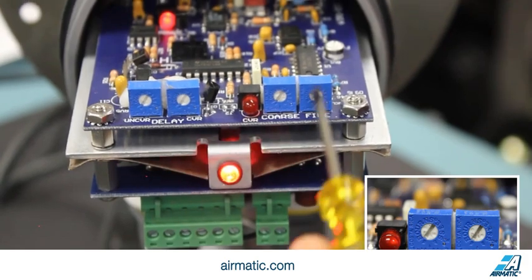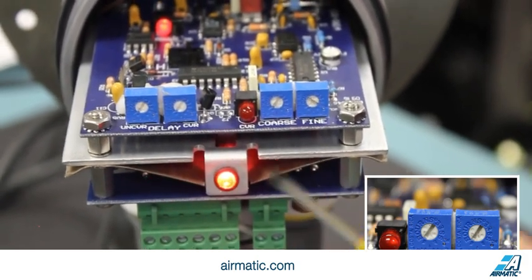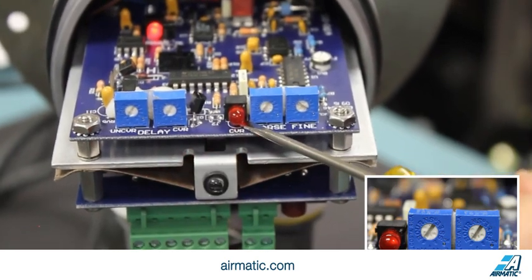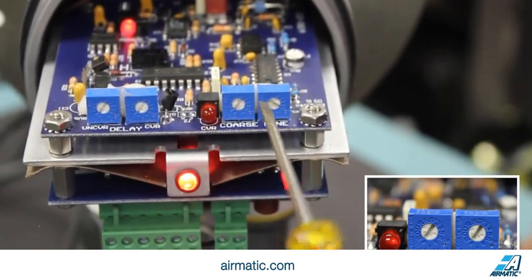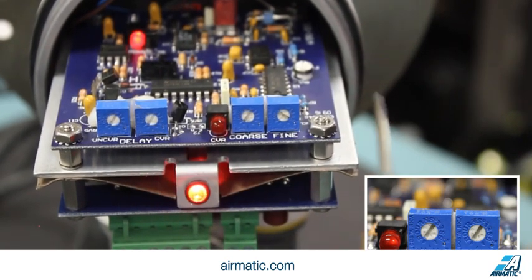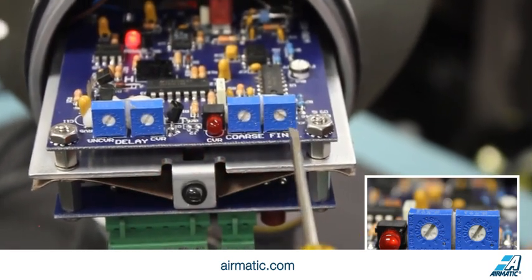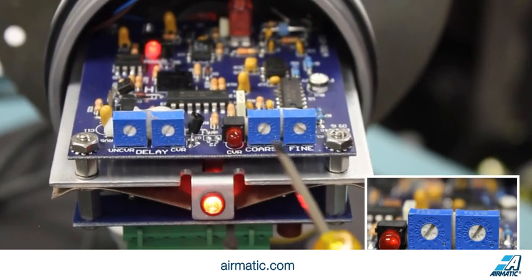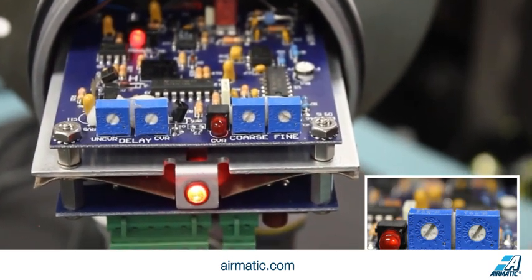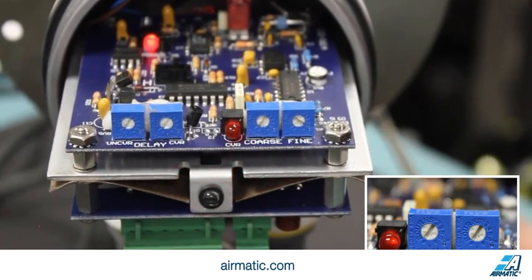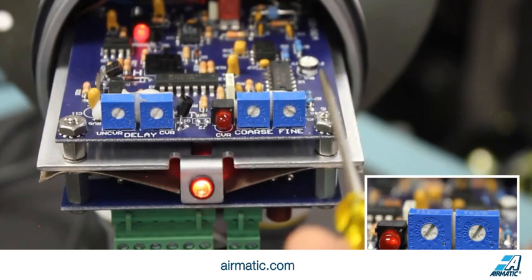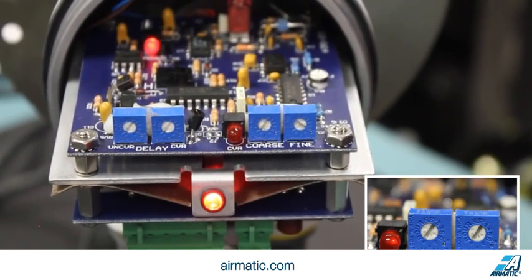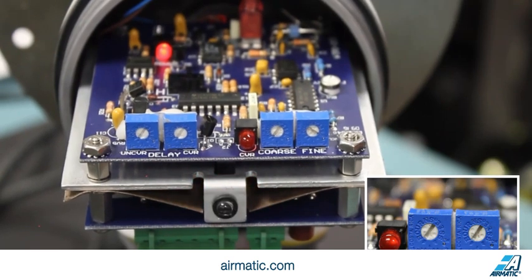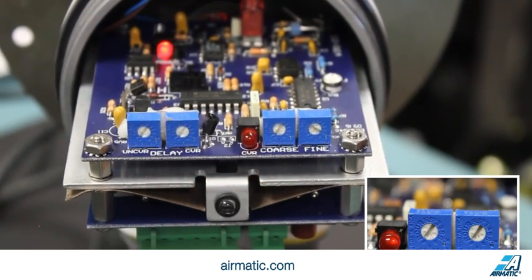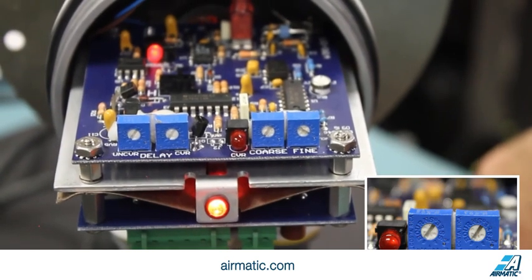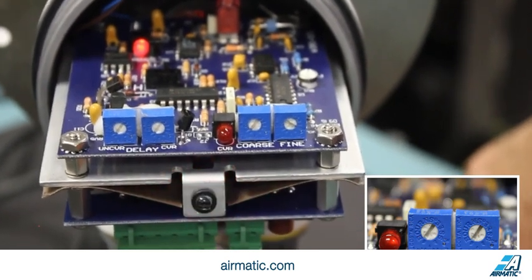So right now at a 1/16 of a turn past the point where the covered LED shut off would be probably where we'd start for a high sensitivity setting. For a medium sensitivity setting, we'd probably turn it about an 1/8 of a turn past the switching point, and that would be about an hour and a half to 3 hours past the switching point. For a low sensitivity, we would probably turn that a 1/4 to half a turn, depending on just how easy the product is to sense. And that's our quick set method to calibrate the probe when the probe is uncovered.